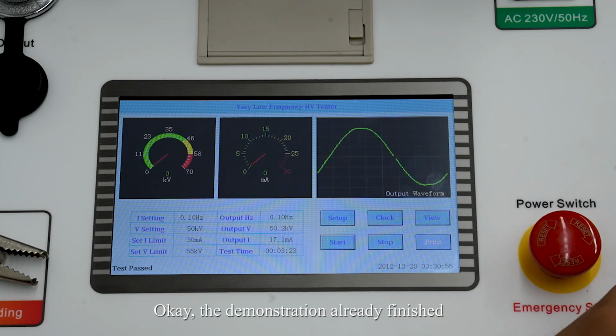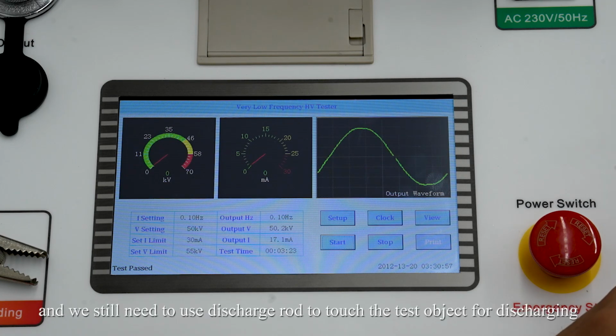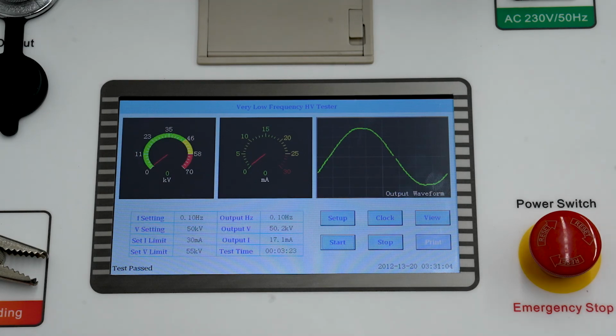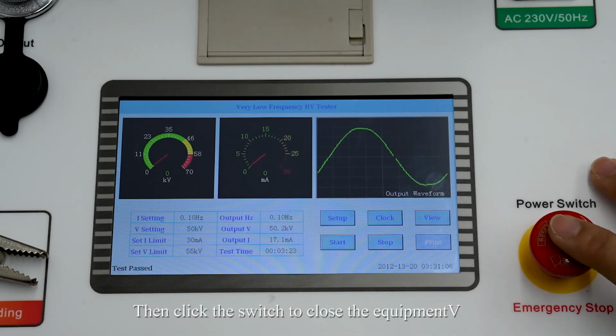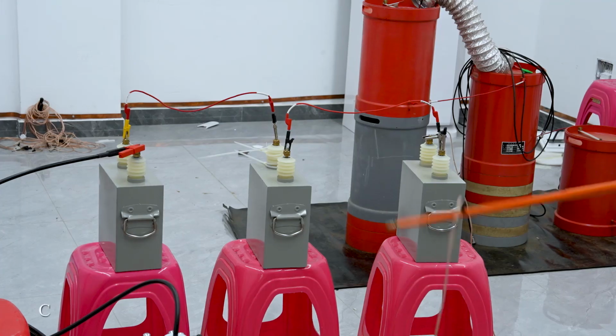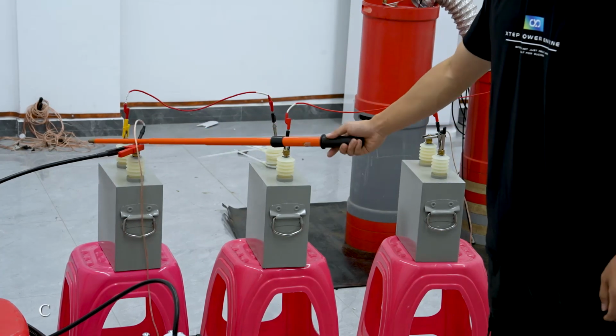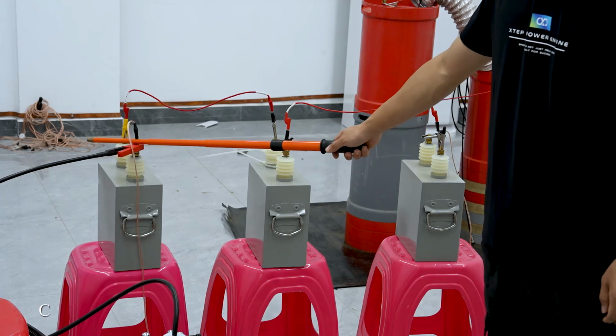Okay, the demonstration is finished, and we will need to use a discharge rod to touch the test object for discharging. Then click the switch to close the equipment. And we will need to use a discharge rod to touch the test object for discharging.